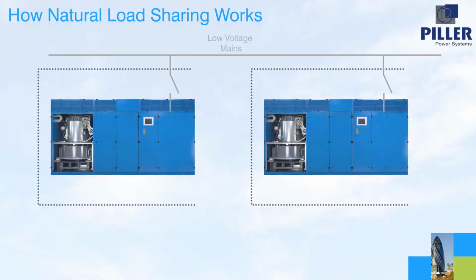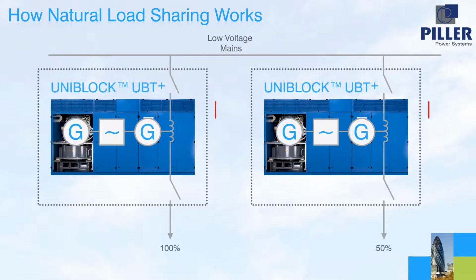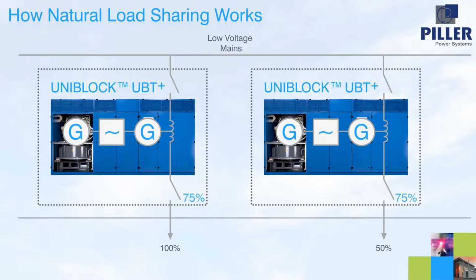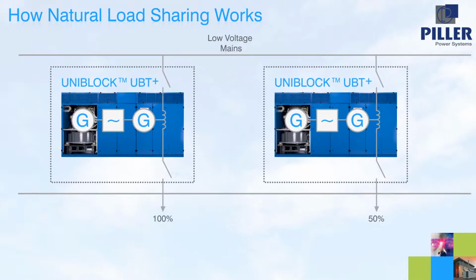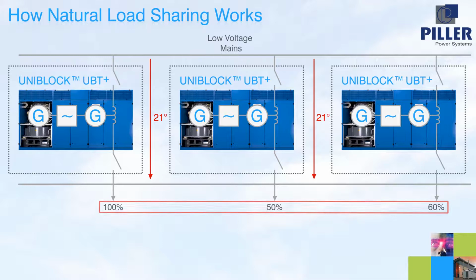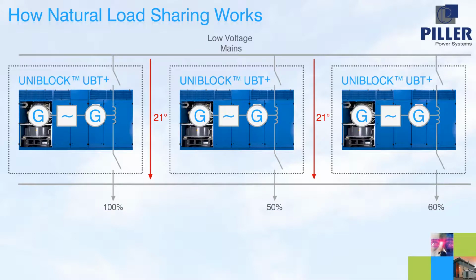Loading a UBT naturally creates a phase angle between the input and output voltage. This phase angle is quasi-proportional to the amount of active power taken by the load. For example, if the full load phase angle is 30 degrees, the phase angle is then 15 degrees at half load. Therefore, parallel UBT units automatically have a common phase angle between input and output. Because of this, all units now have to supply an equal amount of load. In this example, a 210% load is supported by each UPS unit carrying 70%.